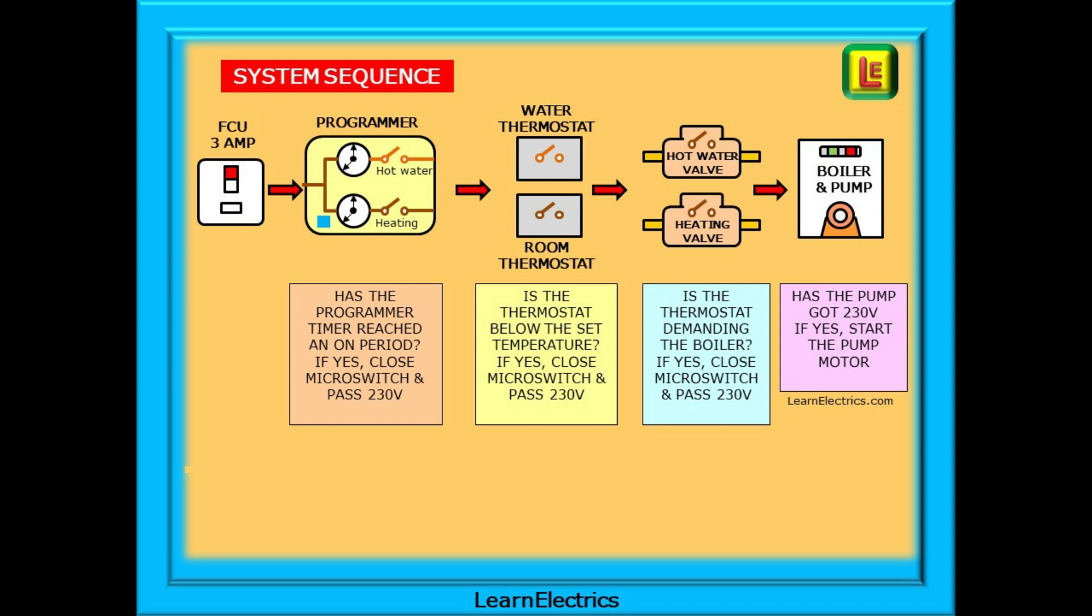We can start at the fused connection unit, the point at which electricity enters the system. We have a programmer to set the on and off periods. And the question is, has the programmer timer reached an on period? If yes, close the microswitch and pass 230 volts to the thermostats. There are separate thermostats for water and heating and again, a question. Is the thermostat below the set temperature? If yes, close the microswitch and pass 230 volts to the valves.